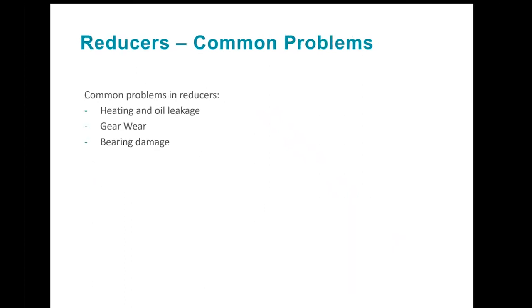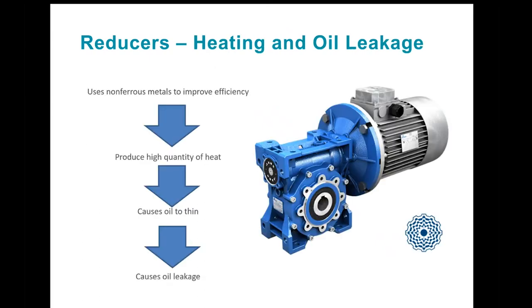Let's take a look at some common problems in reducers. There are three: heating and oil leakage, gear wear, and bearing damage. To improve efficiency, some reducers — in particular worm gear reducers — use non-ferrous metals. Due to sliding friction, this can cause high quantities of heat, which can cause the oil to thin, thereby causing leakage. This is where the oil you choose comes into play. A hotter operating temperature requires lubricants with higher viscosity numbers, because as the oil warms, its ability to resist flow decreases.